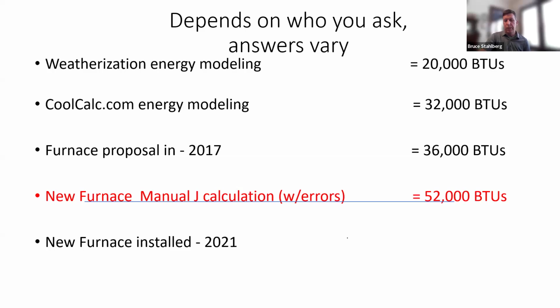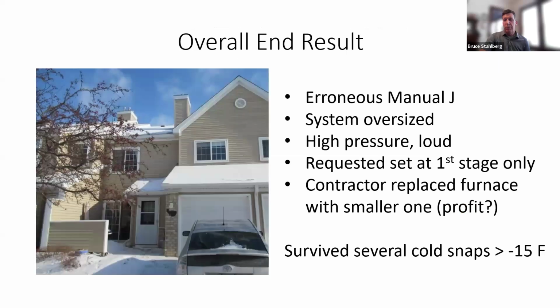So I looked at their calculations, found a number of errors, and I went back to the contractor and said, you know what? You oversized it. It's too big. There were errors in your Manual J, but what we could do is set this furnace to run on first stage only, and in the future you just do a better job, and I'll go ahead and pass it. So I kind of gave him a pass, trying to work with them, saying let's be more careful in the future.